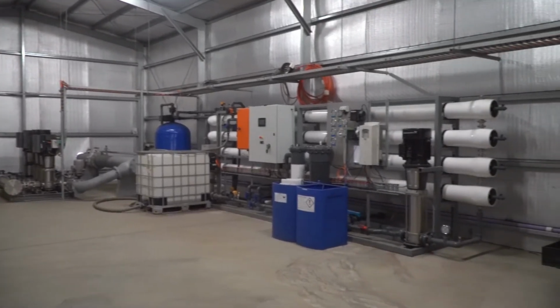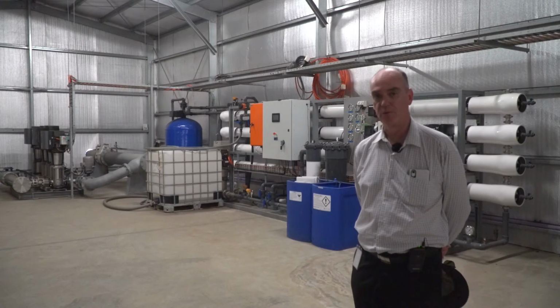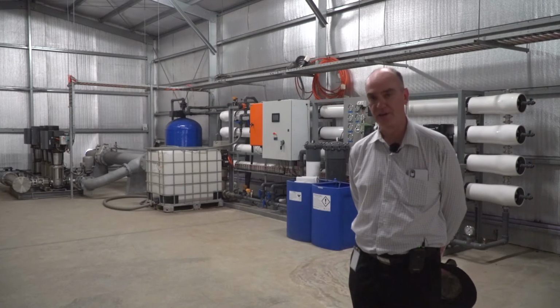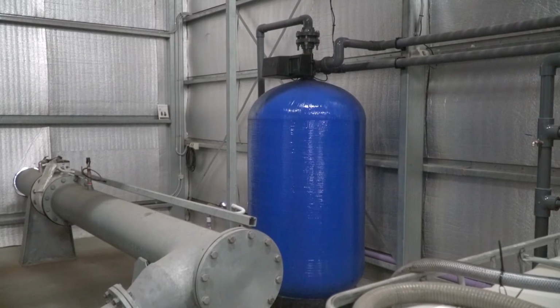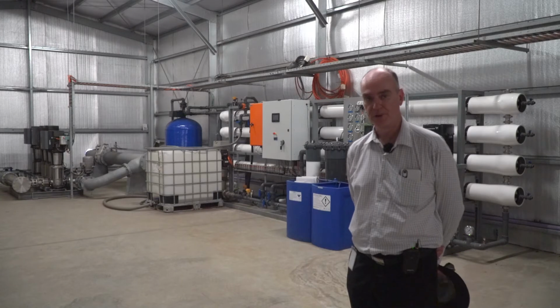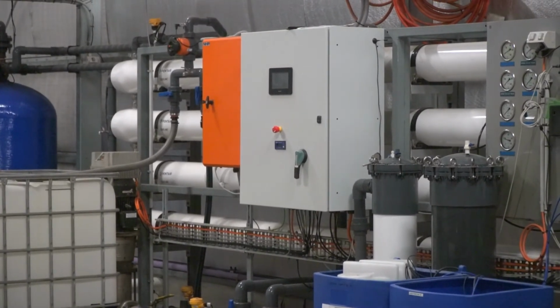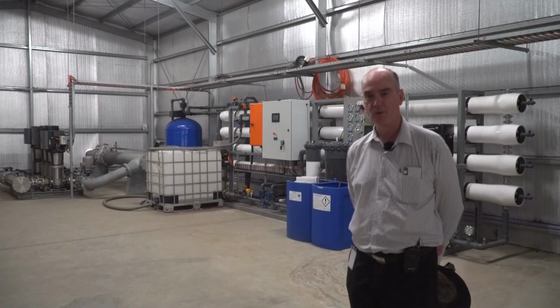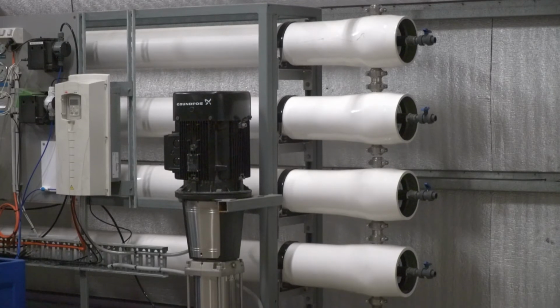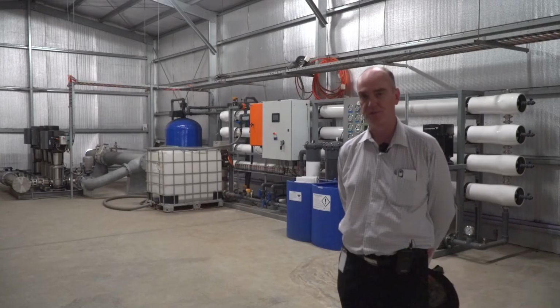All right, so behind me is the membrane ultrafiltration unit. So as I said, we only do this when we're supplying in-house. So our irrigation water supplies don't have this extra treatment stage. So going in-house, just that bit of extra treatment to remove the colour. And then to my right is the distribution pump station. So only 4 pumps at the moment. It's designed to be expanded out to 6 pumps, but as we pick up more customers, we add extra pumps on.